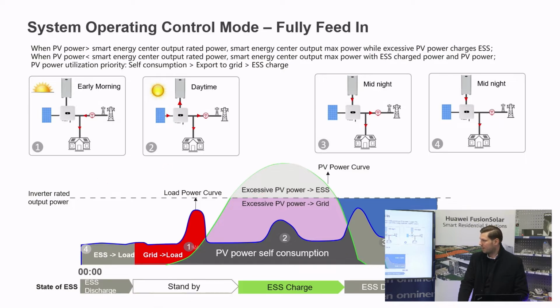If we have an oversized system, like 150 or 180 percent, 100% is the maximum power of the inverter that will be exported to the grid, but this extra power, which normally wouldn't be used, will instead be used to charge the battery. That's why oversizing is not a bad solution — the inverter itself will always make use of that power.